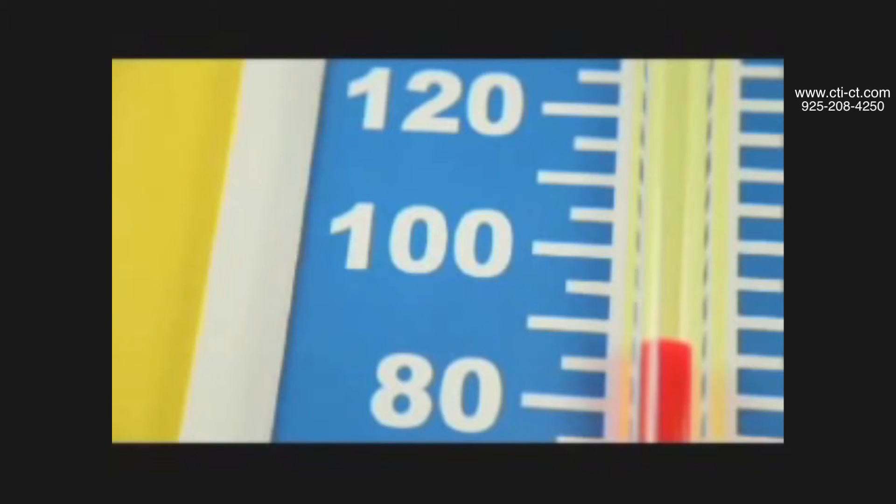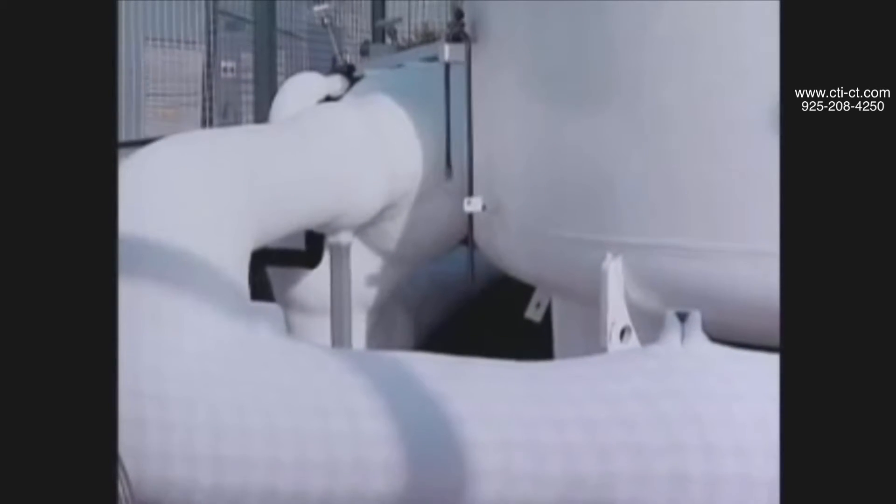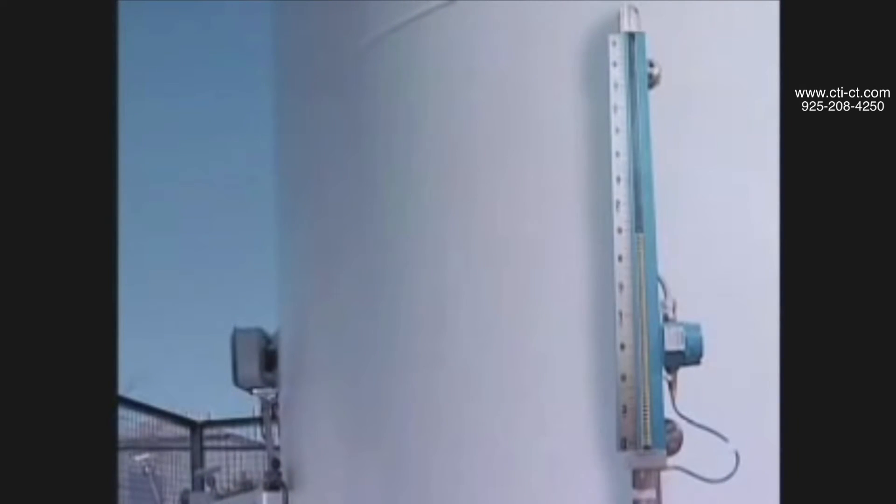How can this happen? It's a hot summer day. The liquid in your storage vessel is being maintained at a controlled cold temperature. However, the small amount of liquid within your magnetic liquid level gauge has warmed up to near or above its critical boiling point.